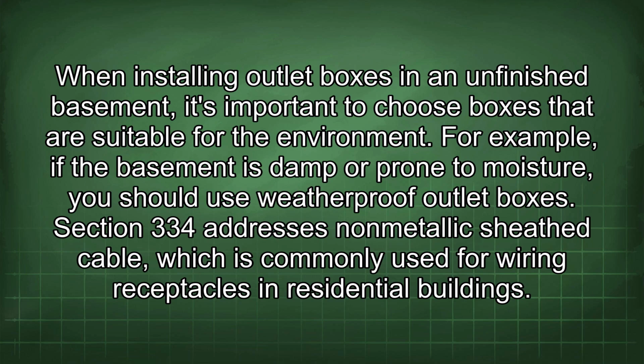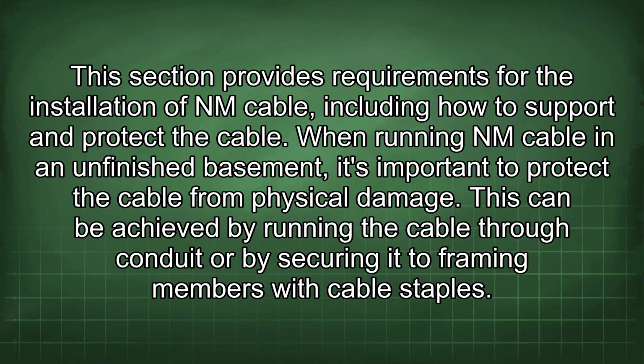Section 334 addresses non-metallic sheath cable, which is commonly used for wiring receptacles in residential buildings. This section provides requirements for the installation of NM cable, including how to support and protect the cable. When running NM cable in an unfinished basement, it's important to protect the cable from physical damage. This can be achieved by running the cable through conduit or by securing it to framing members with cable staples.